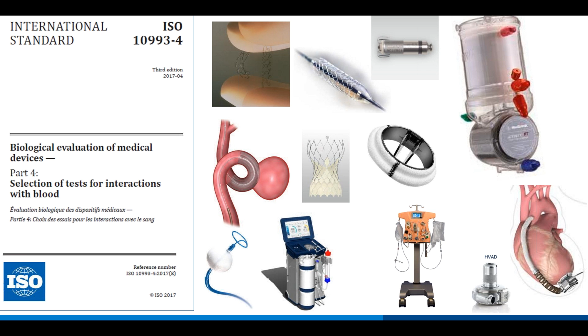And the kind of things we're trying to avoid and the standard is trying to teach is thrombosis associated with these devices, where it happens even in long-term heart valve implants. Actual tissue can grow up over the device and cause weird flow dynamics that can lead to emboli shedding. There's a lot of catheter technology today, and you see catheters in the upper right and in the middle of the screen. These devices perform pretty well even when thrombus forms on them, but if thrombus occludes the delivery lumen, then they will not function properly. Same can be said for cannula, which is shown in the lower right. Their occlusive thrombus will actually make that device fail in the field.